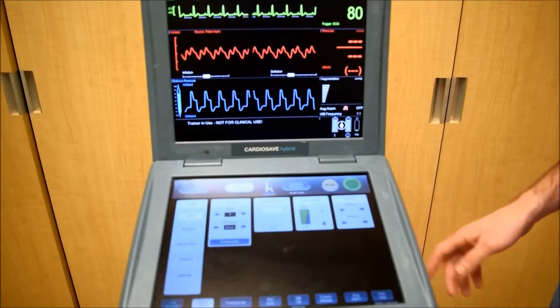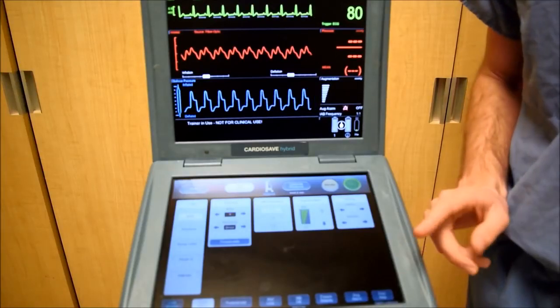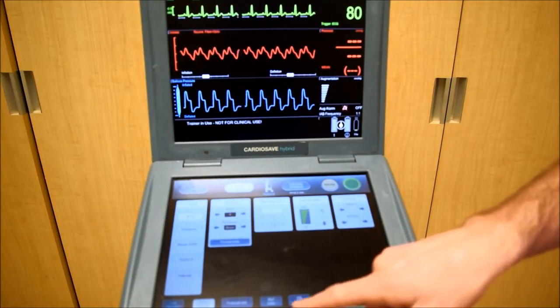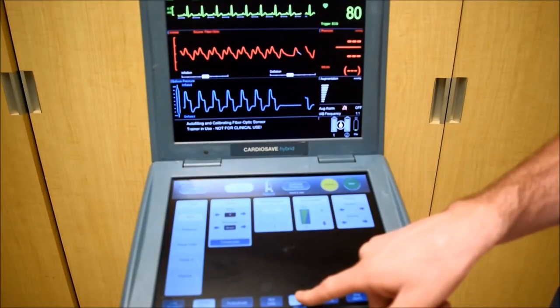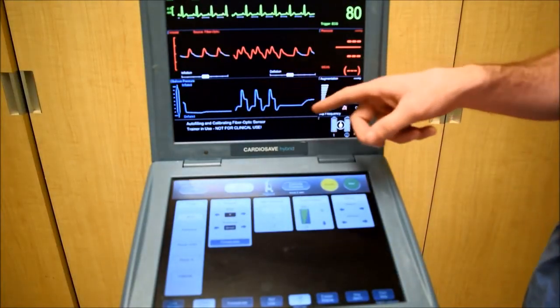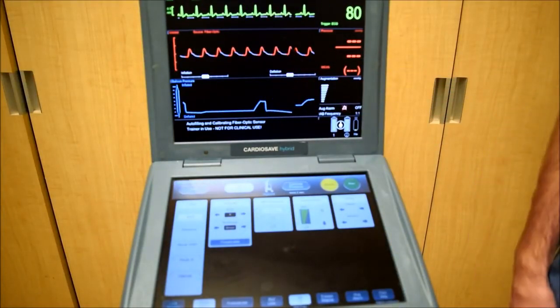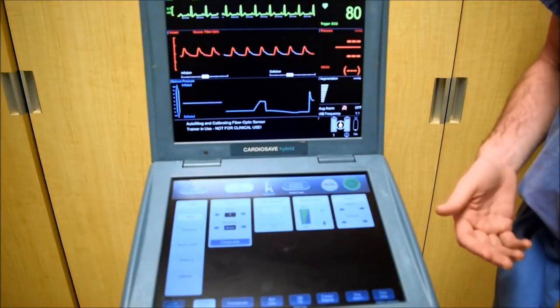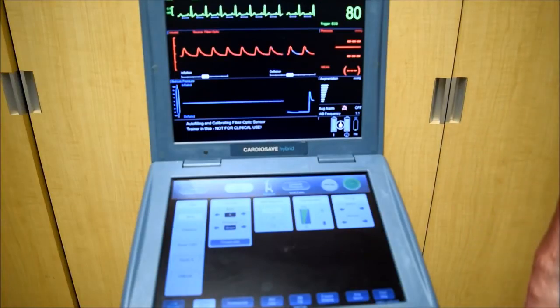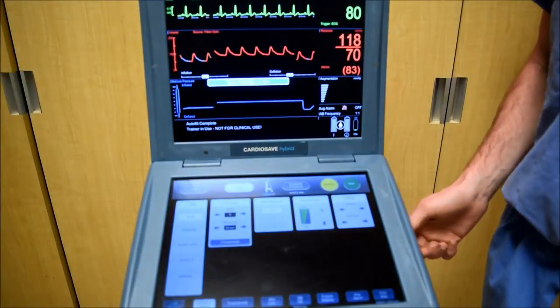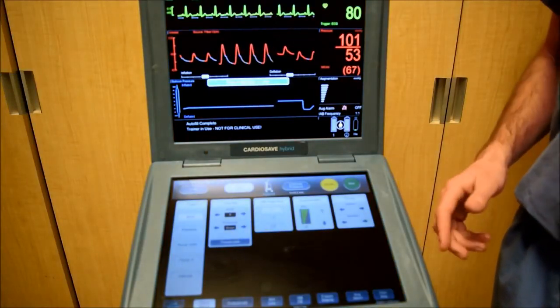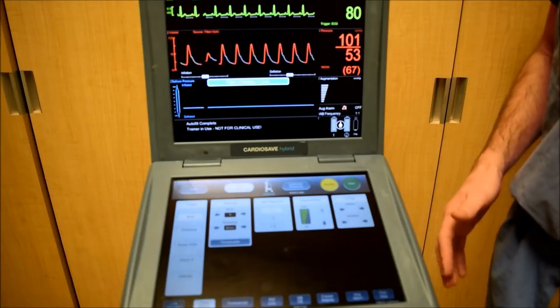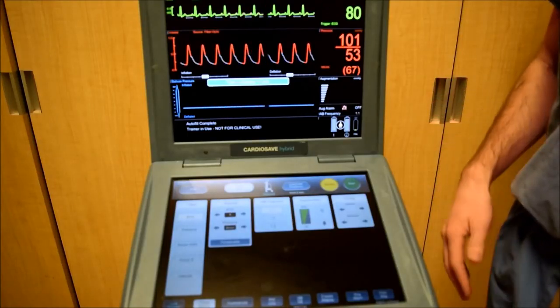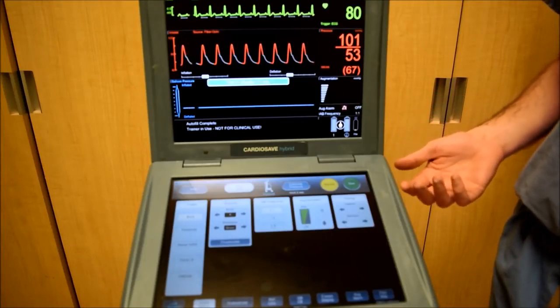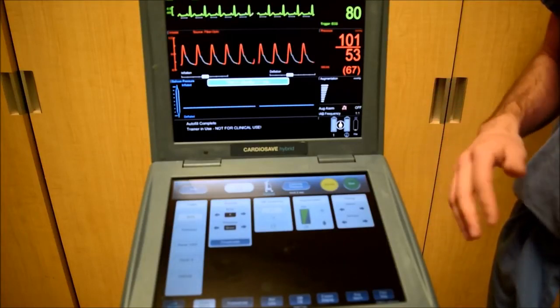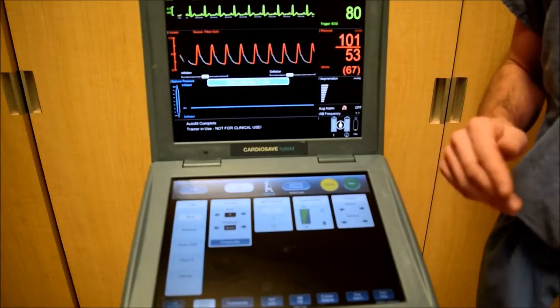If you receive an autofill failure, you can perform another auto refill by holding this button down for 2 seconds. The balloon will now autofill. The balloon does this naturally every 2 hours or so when you're running. This does use helium and can lower the helium tank pressure. However, it doesn't use a whole lot of helium, and if you receive a helium alarm, low-level alarm, you have about 48 hours if you perform no auto refills yourself.